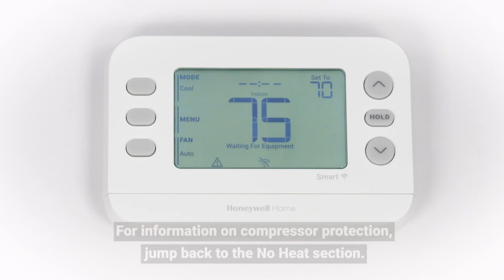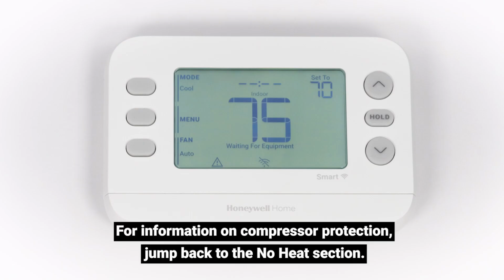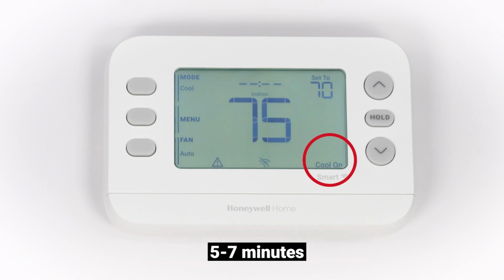The steps for troubleshooting your thermostat for no cooling are similar to troubleshooting for no heating. So, if your system isn't cooling, but Cool On or Wait is flashing on your thermostat, compressor protection may be enabled. Again, allow 5 to 7 minutes for cooling to start. The Cool On message will stop flashing and remain solid.